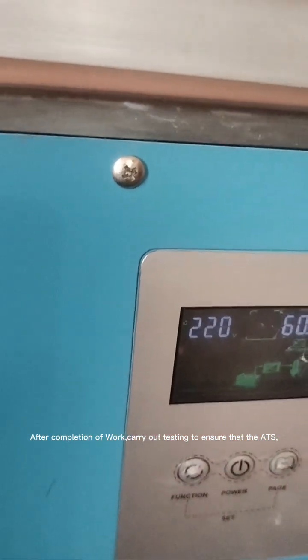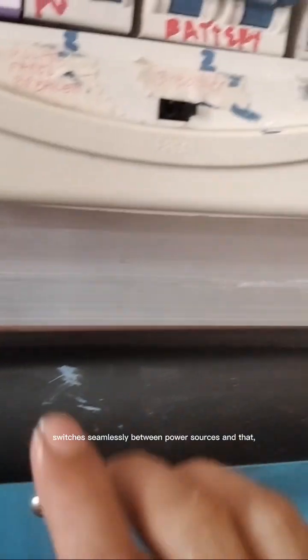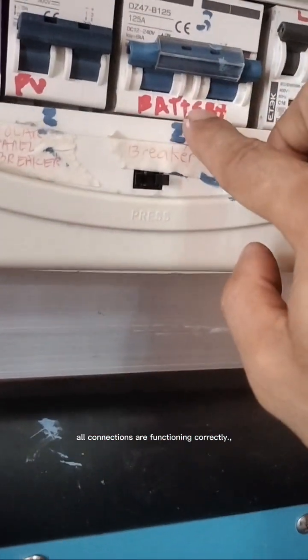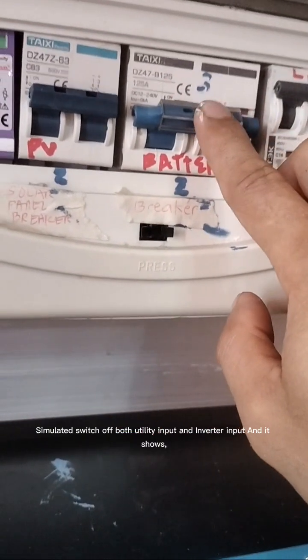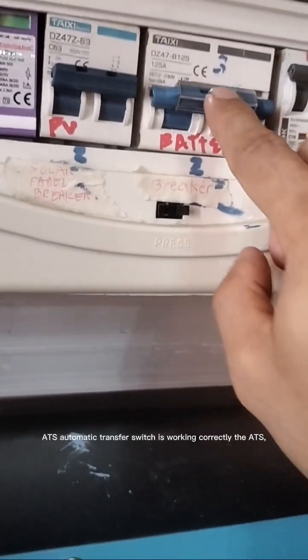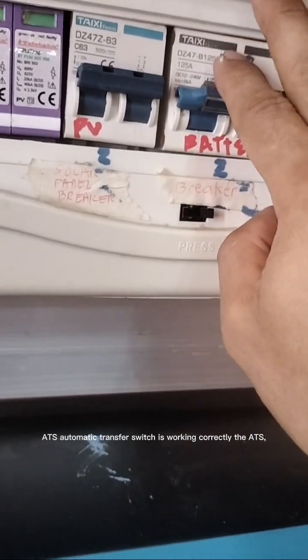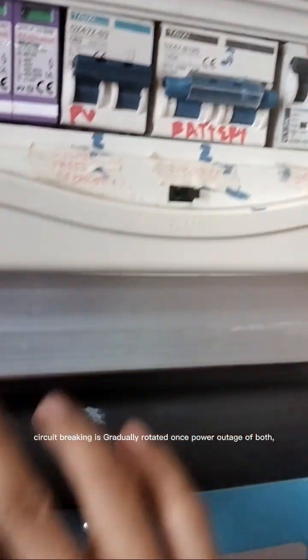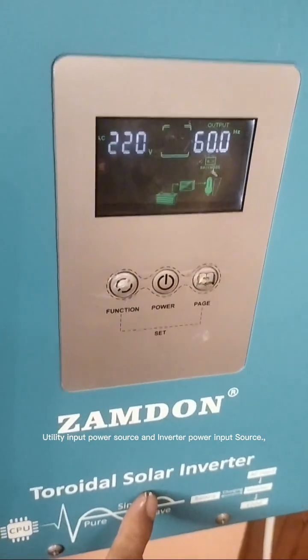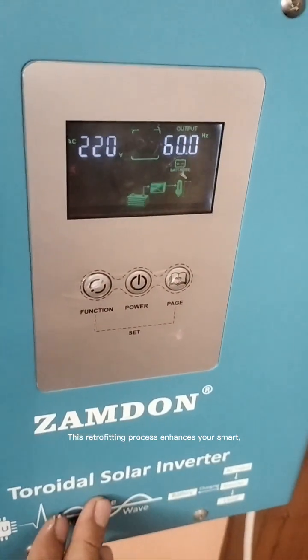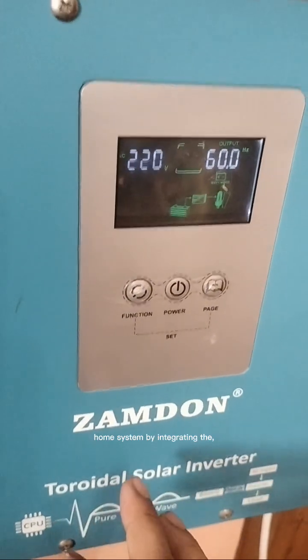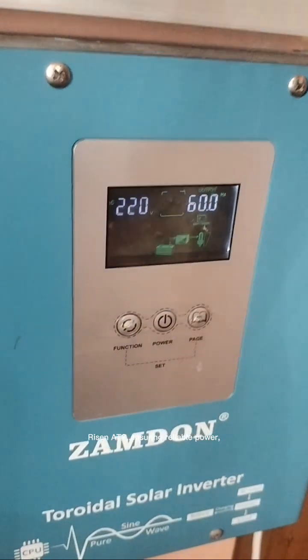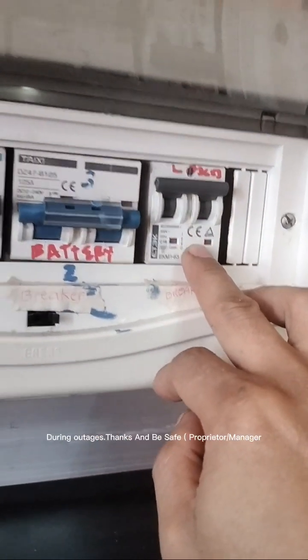After completion of the work, carry out testing to ensure that the ATS switches seamlessly between power sources and that all connections are functioning correctly. Simulate switching off both the utility input and the inverter input, and it shows the ATS automatic transfer switch is working correctly. The ATS circuit breaker gradually rotates once there is a power outage of both the utility input power source and the inverter power input source. This retrofitting process enhances your smart home system by integrating the Risen ATS, ensuring reliable power management and seamless switching between utility and solar power during outages.